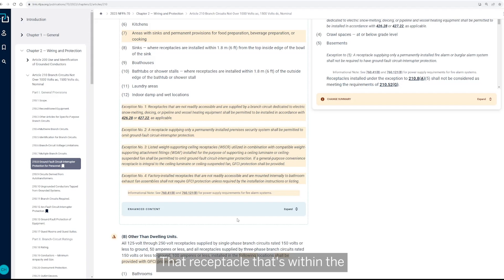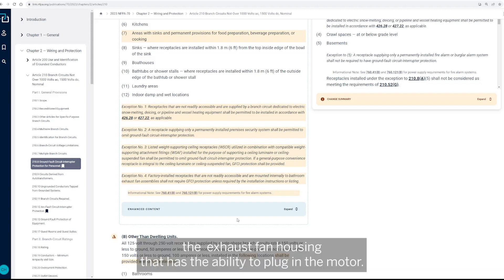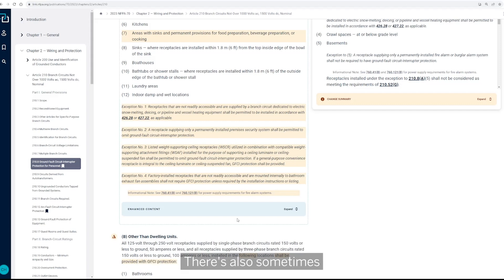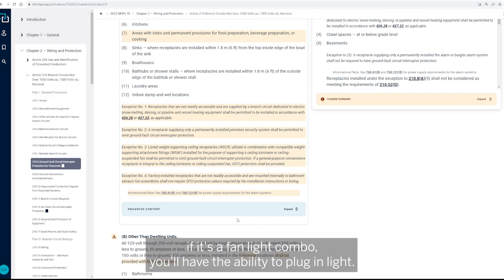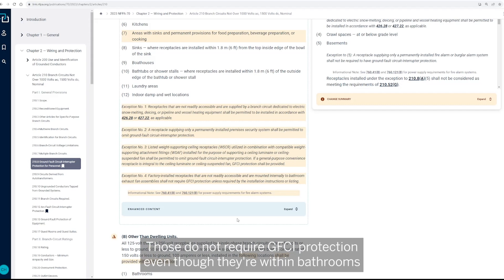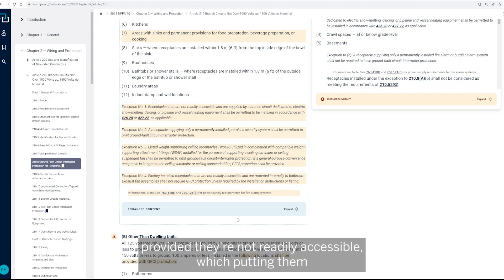So this is that receptacle that's within the exhaust fan housing that has the ability to plug in the motor. There's also sometimes if it's a fan light combo, you'll have the ability to plug in the light. Those do not require GFCI protection, even though they're within bathrooms, provided they're not readily accessible.